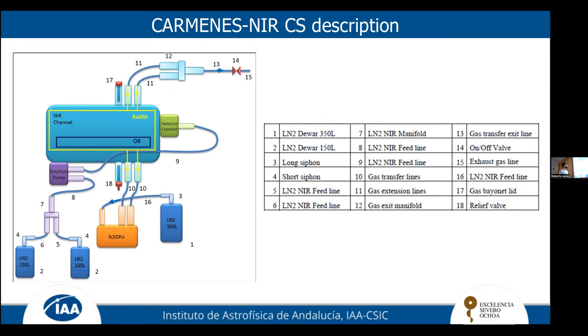This gives liquid nitrogen to the orange part, the next step, what we call the nitrogen gas preparation unit, that basically evaporates the liquid nitrogen and gives us a very stable flow of gas, because this is what we use to cool down the system.